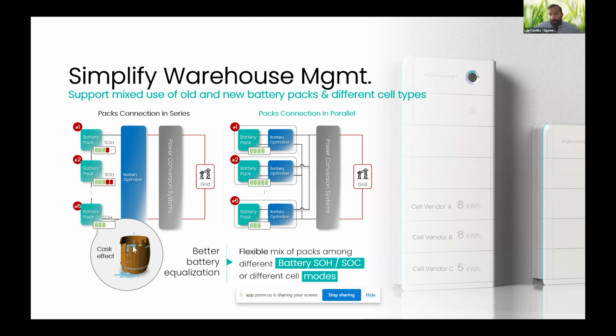The other advantage of our architecture is that all battery packs are connected in parallel with the energy controller. So if one of them fails, it just disconnects from the bus, and the other battery packs are not affected; they continue charging or discharging with the bus. There isn't really a bypass scenario, because we're not bypassing anything, since all battery packs are connected in parallel. This is a huge advantage for the downtime of your equipment. If one battery pack fails, only that pack will be out, and the rest of the unit will continue working normally.